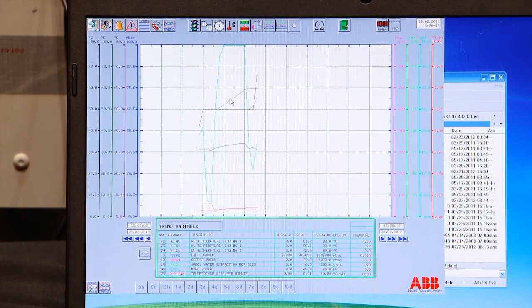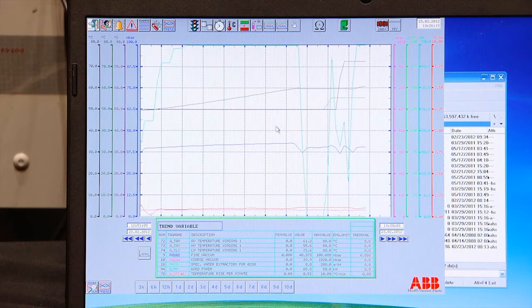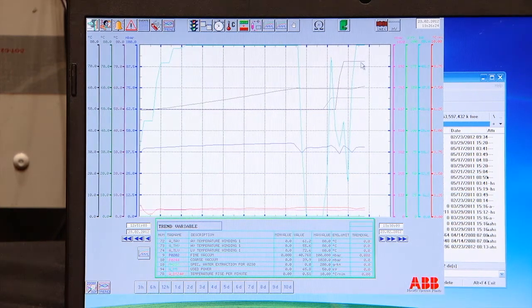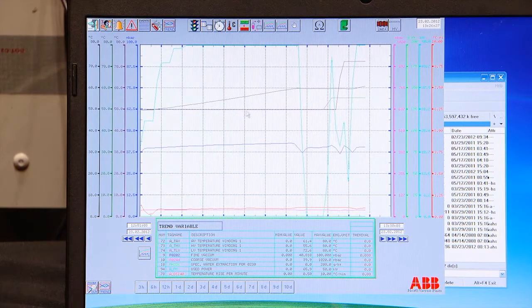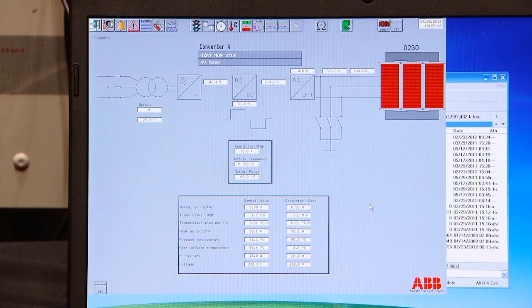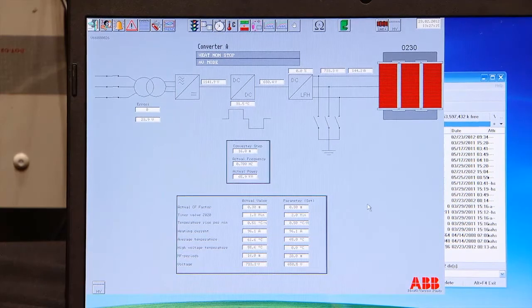Here we have the average temperature, here we have the high voltage and low voltage temperature. If we zoom in here, he's adjusting these two levels to the result we got. So they remain constant here because we do not measure them. We don't know what's happening with them. And then you have a step temperature here. That, as we discussed before, cannot happen, but we cannot measure the separate winding temperatures in any other way. So we have selected to keep the constant temperature and make the step. When we're coming into the heating break, we can make the suction capacity measurement on the vacuum pumps.